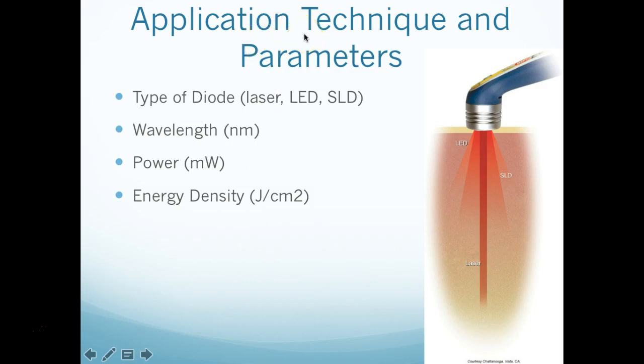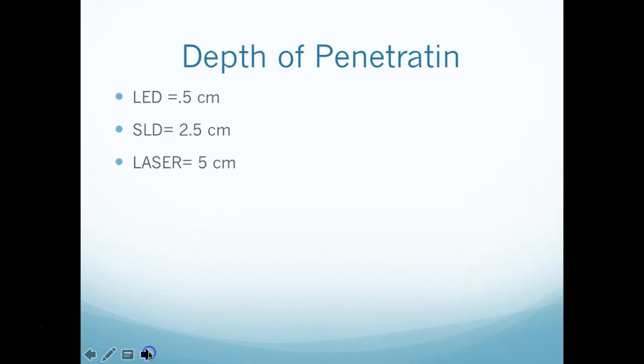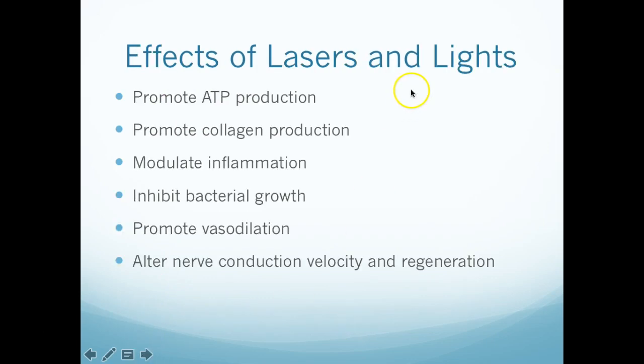For application and parameters: the laser is monochromatic and coherent — it goes straight down and penetrates. The SLD spreads out a little bit more, and the LED fans out even more — it's more non-coherent. In terms of penetration depth, the laser goes the deepest, similar to ultrasound — approximately five centimeters or about two inches. The SLD goes in about an inch, and the LED is very superficial, even less so than a superficial heat pack.